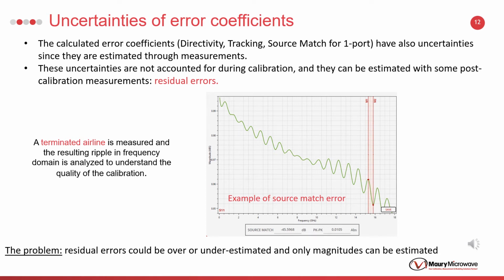Therefore, the calculated error coefficients also have uncertainties. It is possible to estimate residual errors of a calibration with post-calibration measurements. Usually a short terminated airline is used for the measurement. The ripples in the measured data show the amount of residual errors of the calibration.